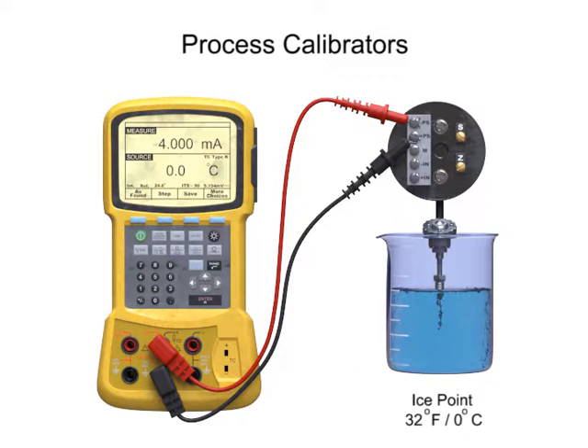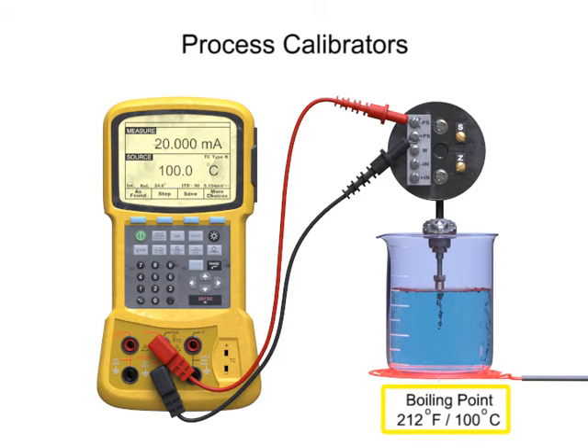To perform the measurement, the process calibrator is programmed to the specific RTD type. The accuracy is determined by measuring the temperature of water at 0 degrees Celsius and 100 degrees Celsius, representing freezing and boiling points of water. Connecting the RTD output to the calibrator, the measured temperature is displayed using the measure function.